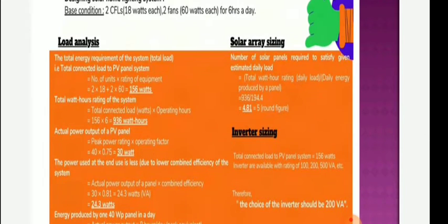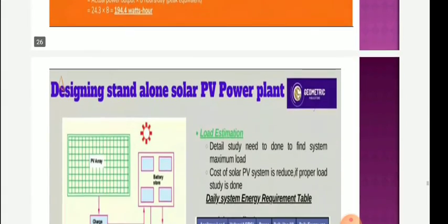Similarly, for inverter sizing, the load is 156 watts, so the nearest standard size is 200 watts. So it is taken as 200 volt amps. So 5 panels and an inverter with a capacity of 200 volt amps are required for the system.